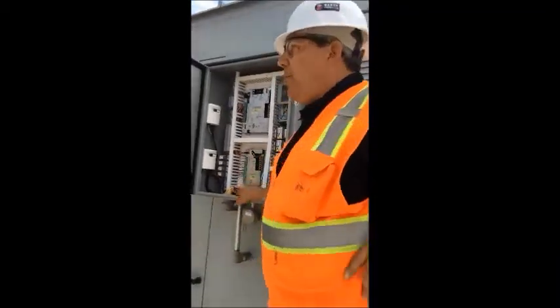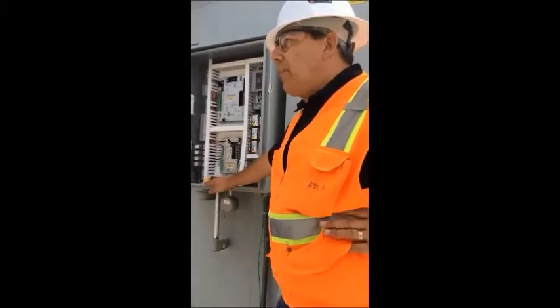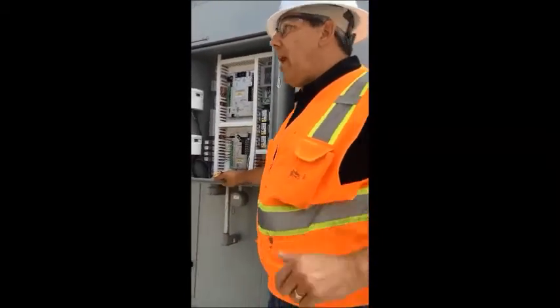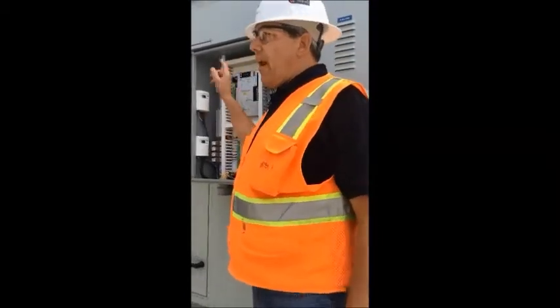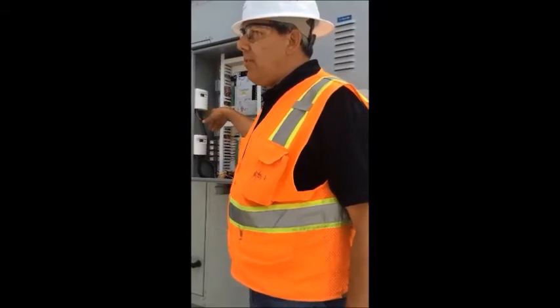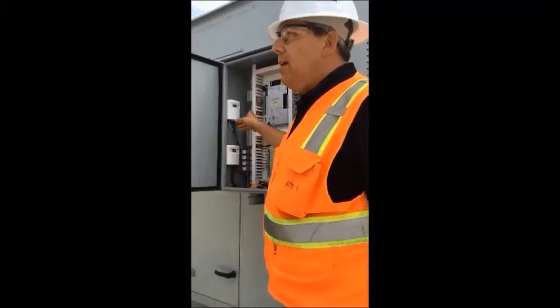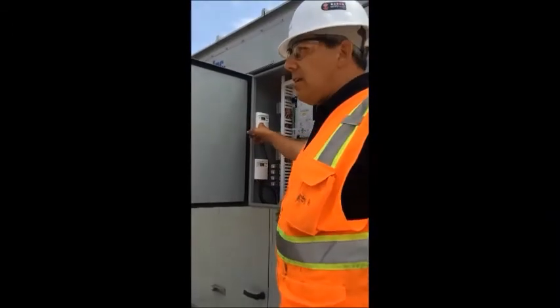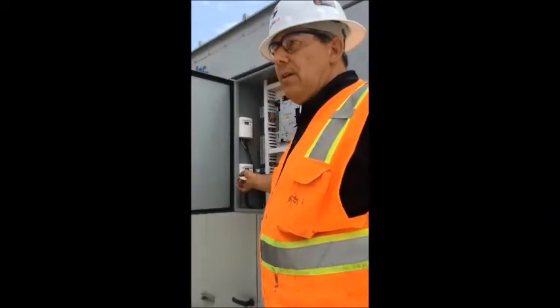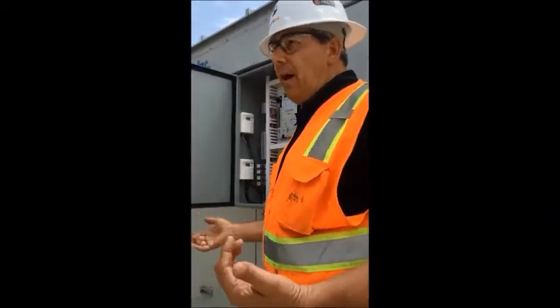So right now they must be doing static pressure reset. So right now, hey Jeff, the static pressure is running at 0.728 because they're doing static pressure reset on the VAV boxes. So this is duct static pressure, this is building pressure. So when you come up here, you can see the references up near the air handler.